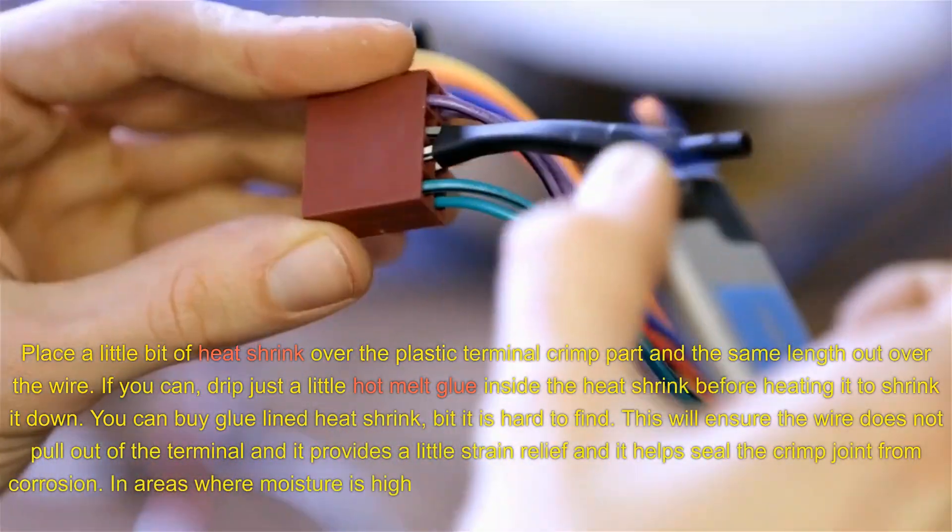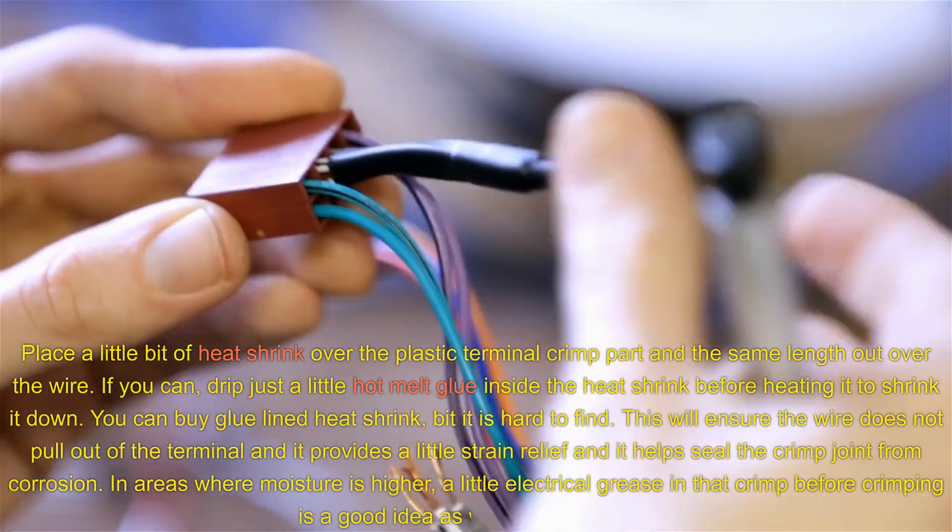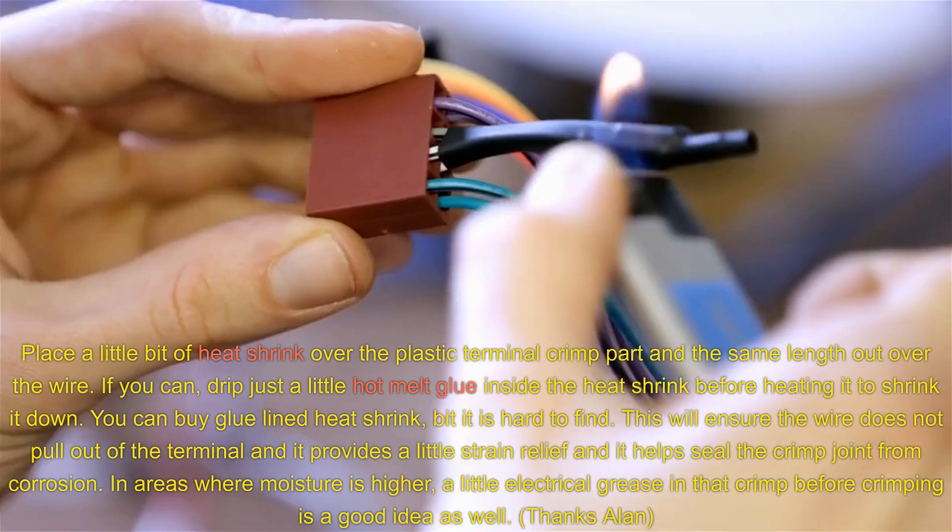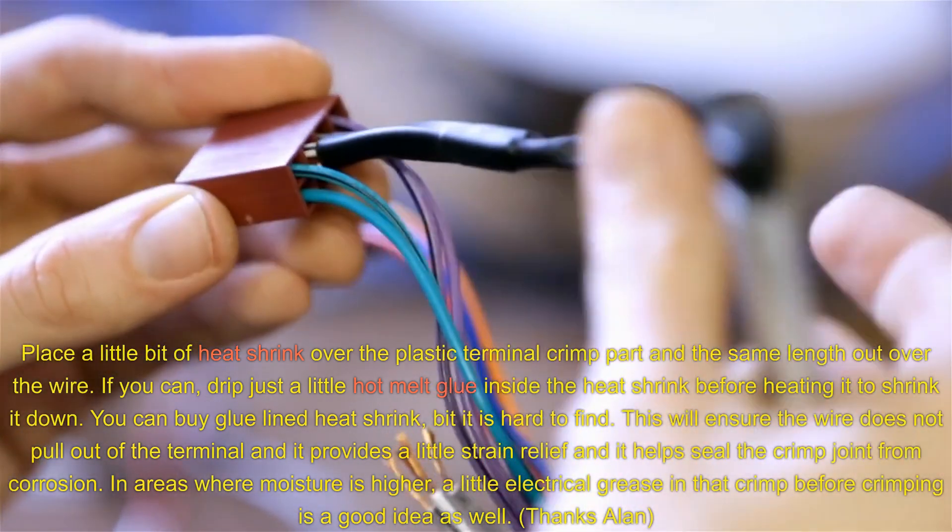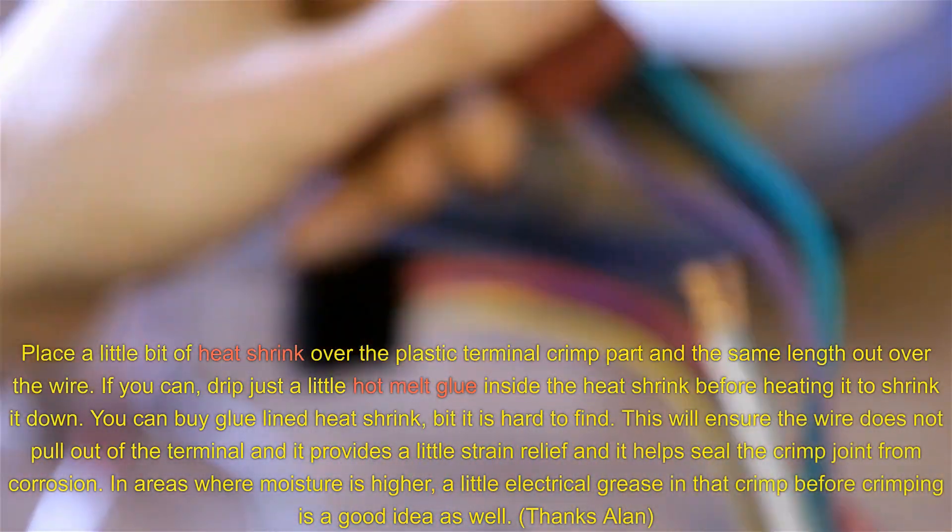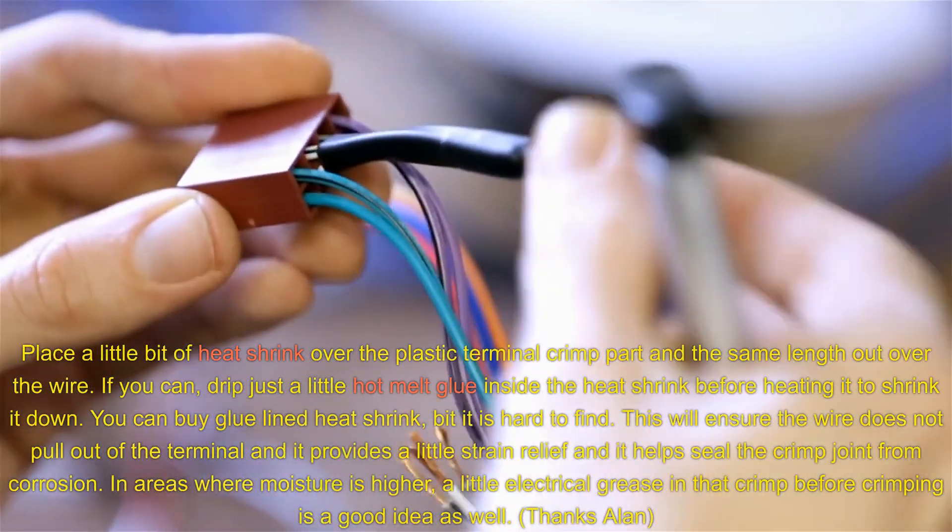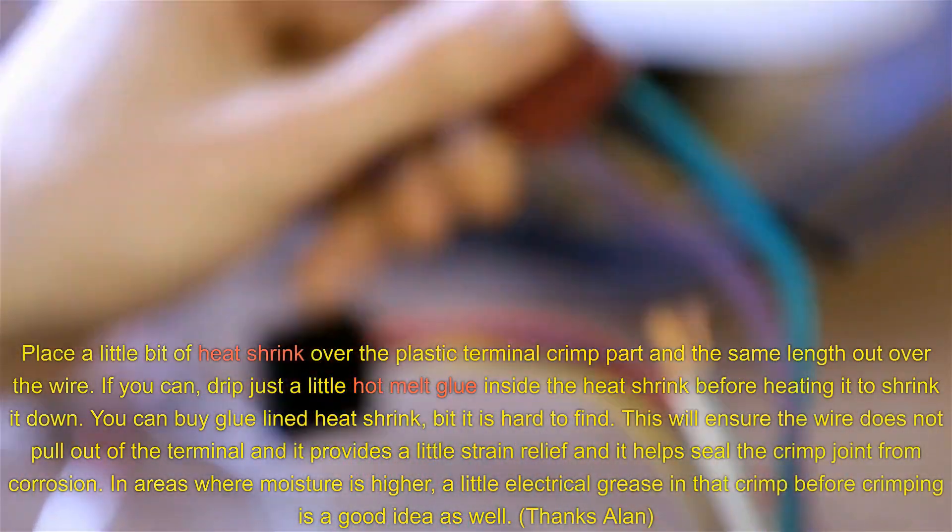Place a little bit of heat shrink over the plastic terminal crimp part and the same length out over the wire. If you can, drip just a little hot melt glue inside the heat shrink before heating it to shrink it down. You can buy glue-lined heat shrink, but it's hard to find. This will ensure the wire does not pull out of the terminal and it provides a little strain relief and it helps seal the crimp joint from corrosion.